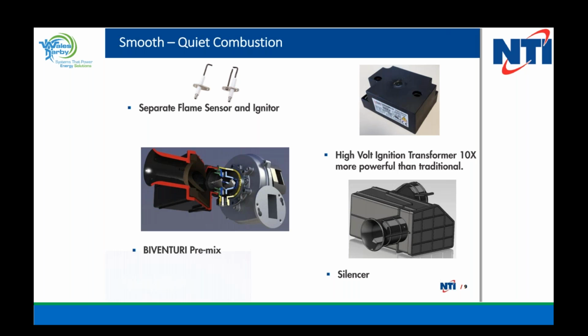You can see our premix on the left-hand side there of how we mix our air to gas ratio. Yeah, they're good service points, Jim, for maintenance there, right? We got to make sure that Venturi is clean and free of dirt and debris, and we want to check those during annual maintenances.